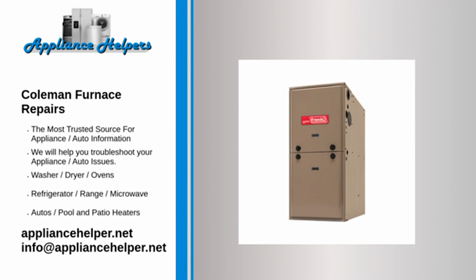Coleman furnace starts then stops. The flame sensor monitors the burner to detect whether or not a flame is present. If the flame sensor is defective, it might fail to detect a flame. If the flame sensor does not detect a flame, the control board will shut off voltage to the gas valve to prevent the furnace from heating. Sometimes, if the flame sensor is dirty, it will fail to detect a flame. Try cleaning the flame sensor with a fine abrasive pad. If the furnace still doesn't heat, replace the flame sensor.